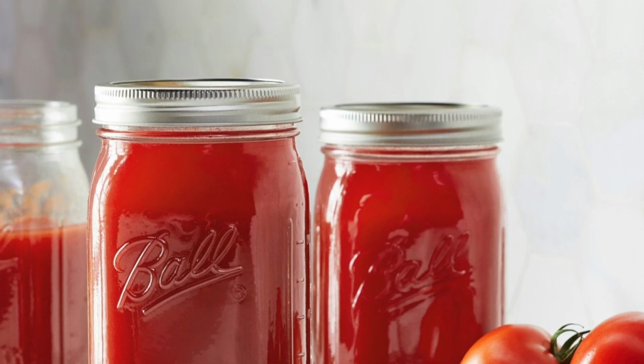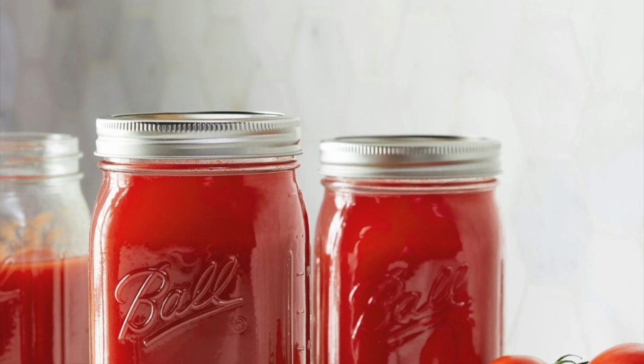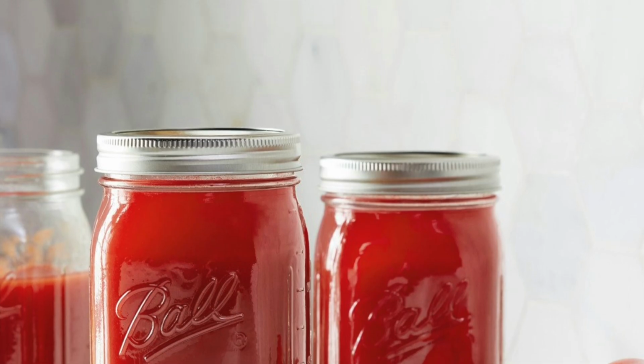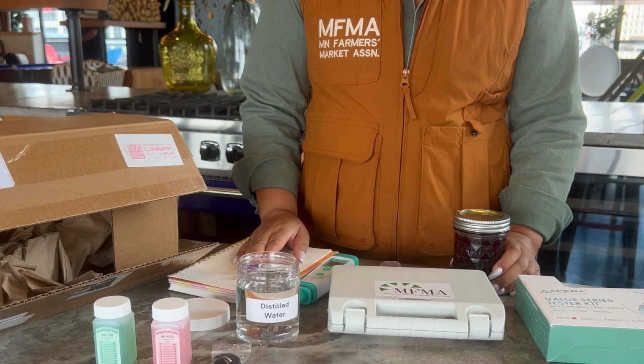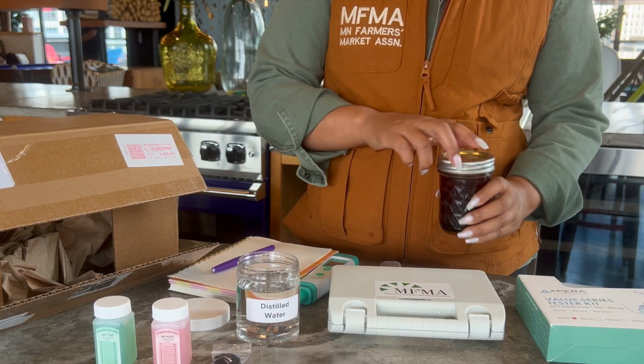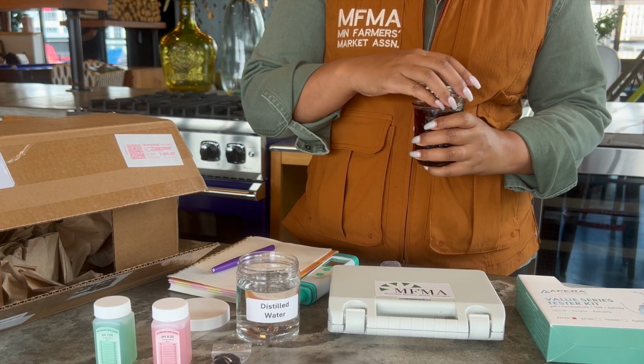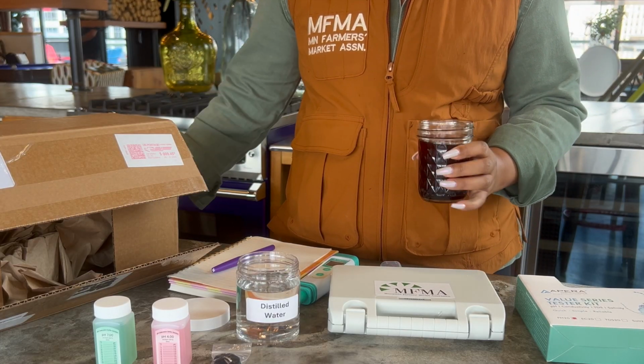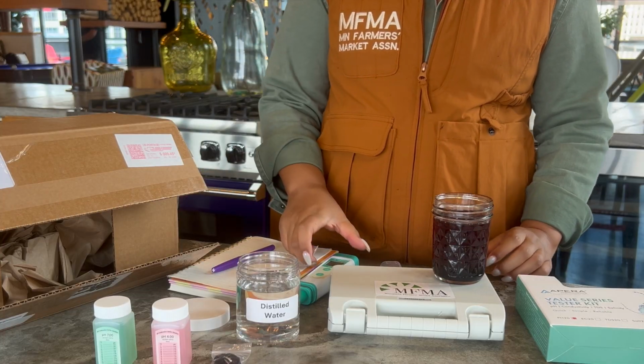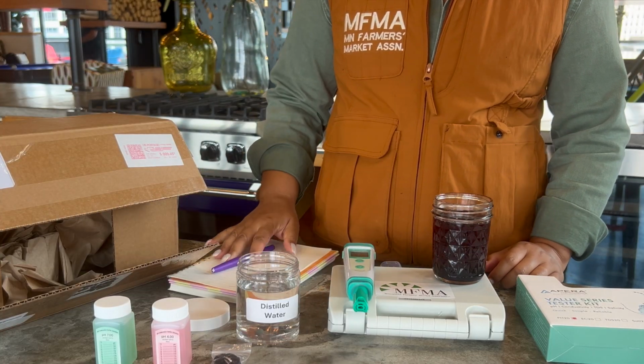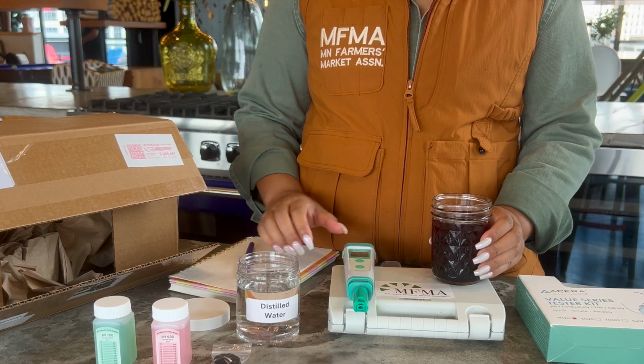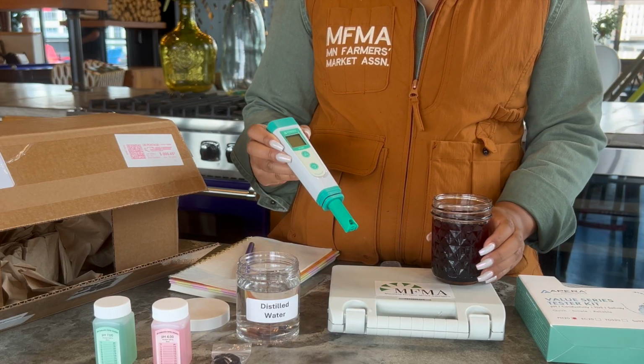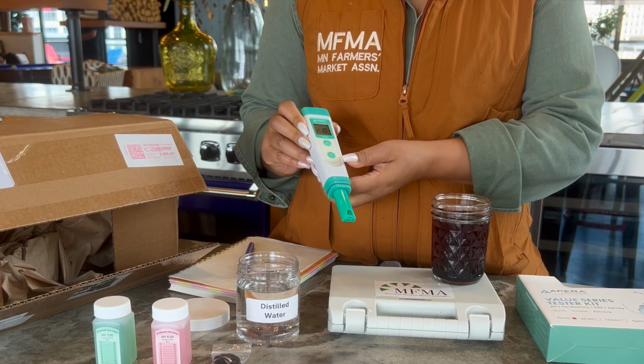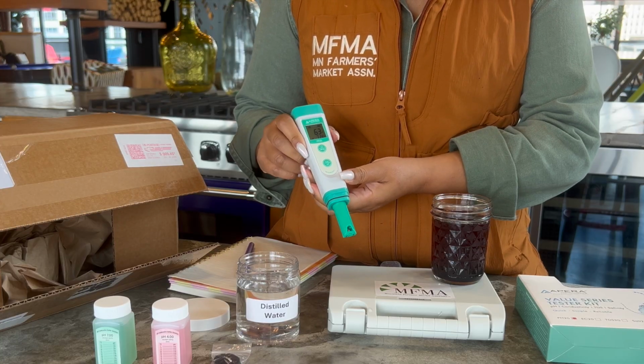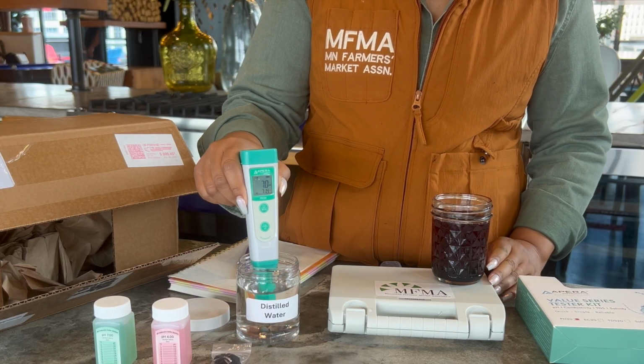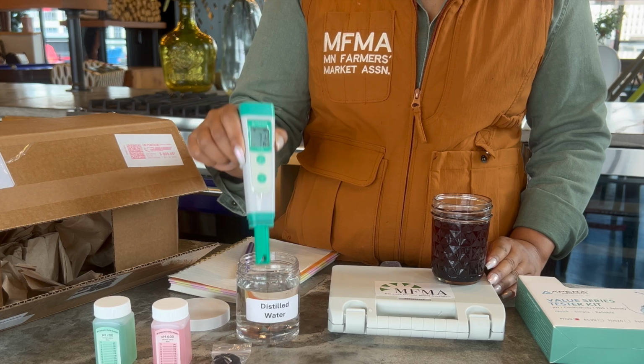Food samples must be at room temperature to get an accurate pH measurement. Pour a small amount of your ready-to-test food into a container to test it. There should be enough food to completely cover the end of the calibration probe. Step 1, with your pH meter calibrated, short press the measure button to turn on the meter. Step 2, rinse the probe in your distilled water, shake off the excess water.